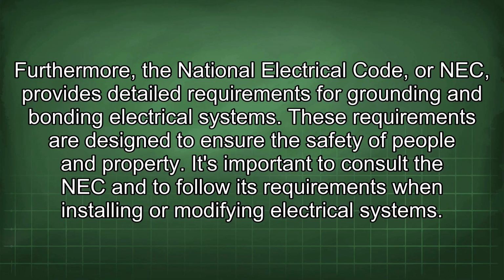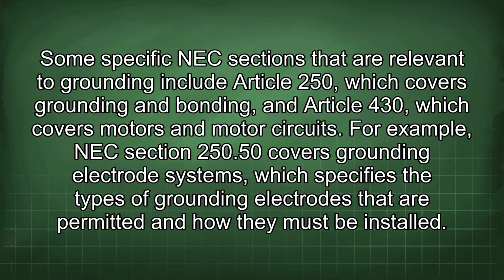It's important to consult the NEC and to follow its requirements when installing or modifying electrical systems. Some specific NEC sections that are relevant to grounding include Article 250, which covers grounding and bonding, and Article 430, which covers motors and motor circuits. For example, NEC Section 250.50 covers grounding electrode systems, which specifies the types of grounding electrodes that are permitted and how they must be installed.